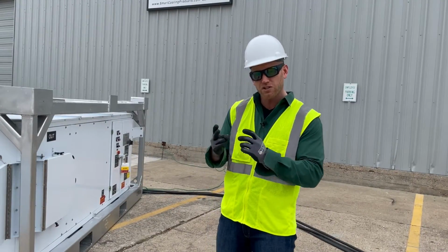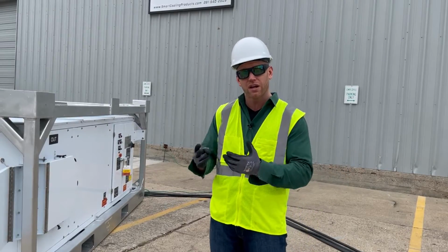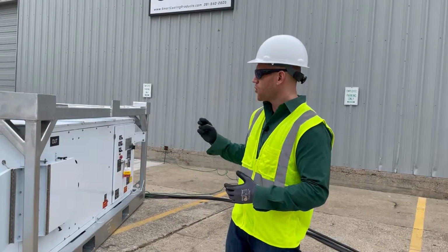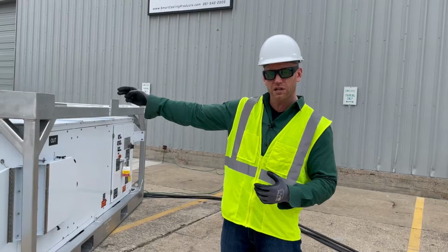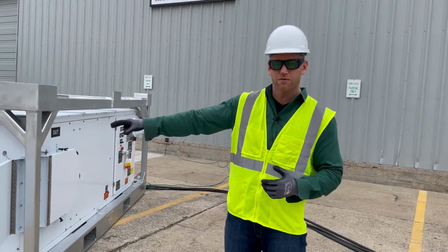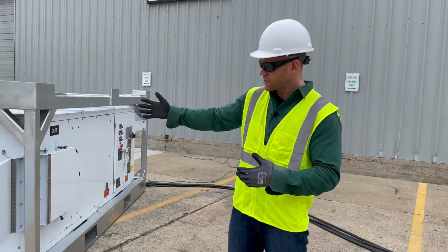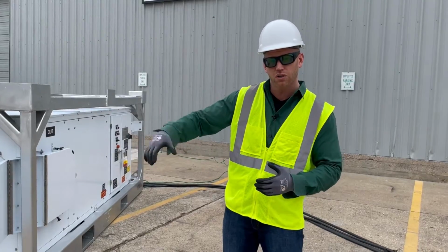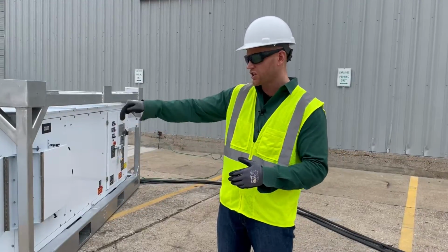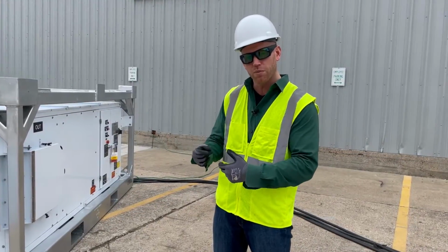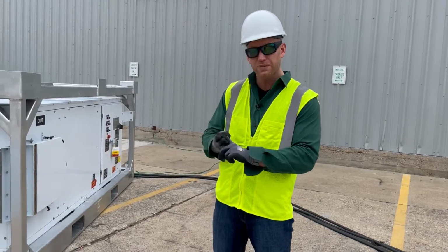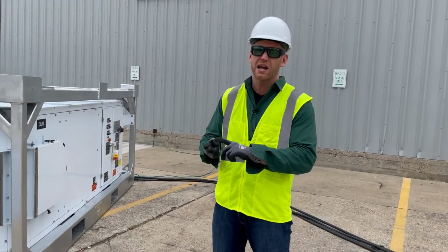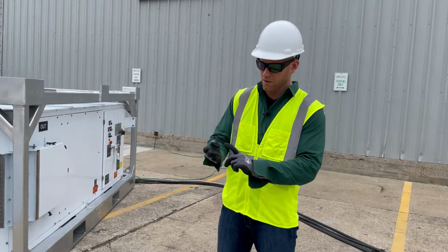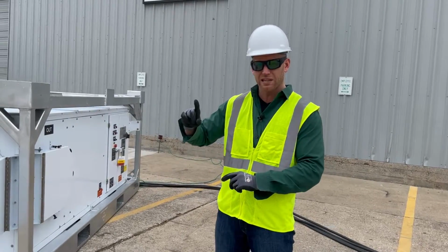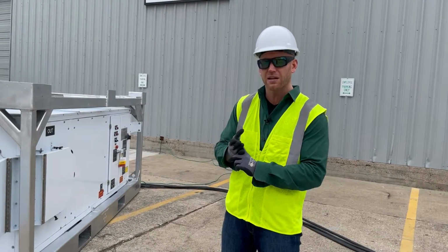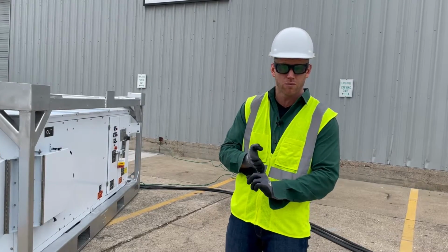Step number 2, make sure you have a clear path of airflow through the machine. That means opening up typically all of the return air connections and the correct amount of supply connections. Now obviously you would have your portable ductwork hooked up, but we don't have any hooked up so that you can actually see how the blower is spinning. Step number 3, inspect those filters. Make sure they are white, clean, and ready to run. Step number 4, go ahead into the drain pan cabinet, inspect the drain pan and make sure there's nothing in there that could damage the blower.